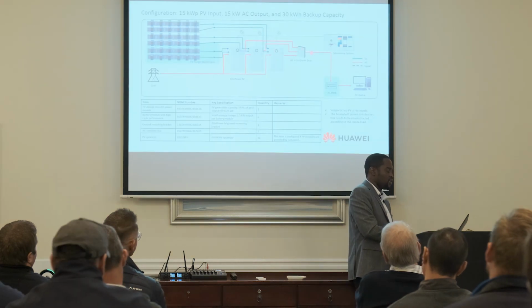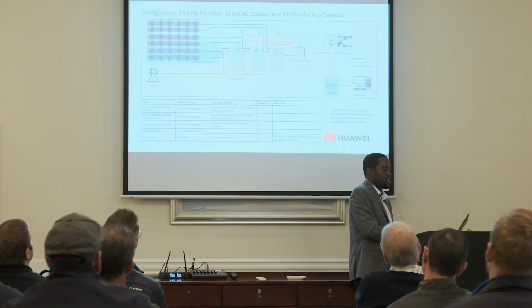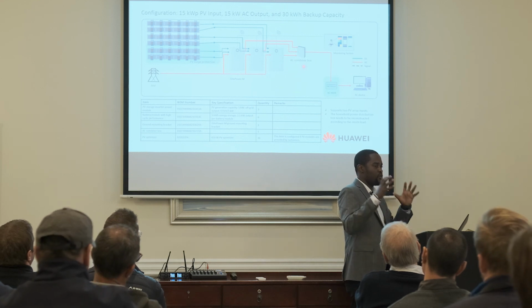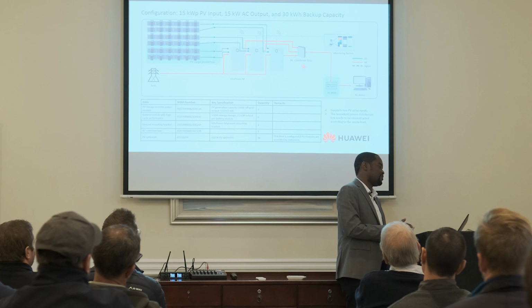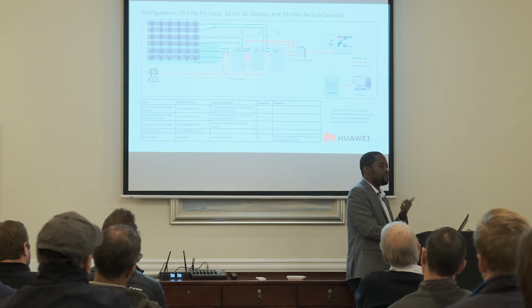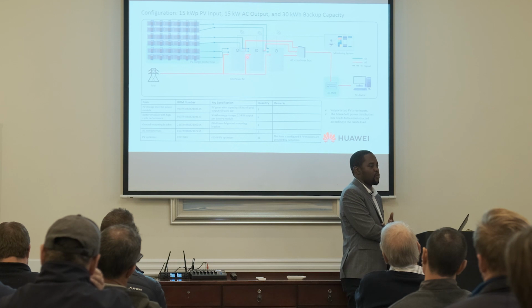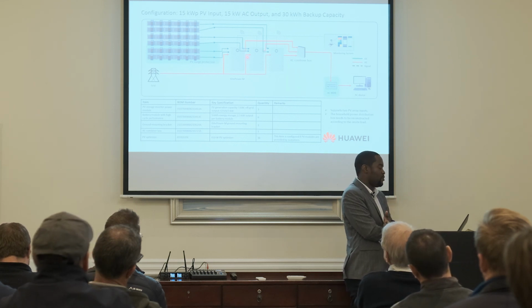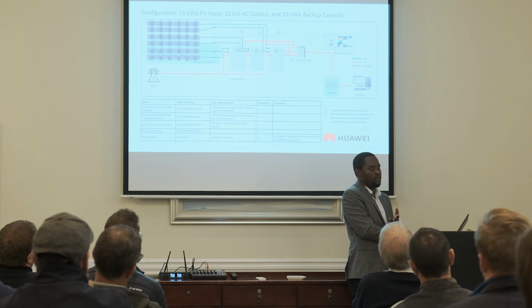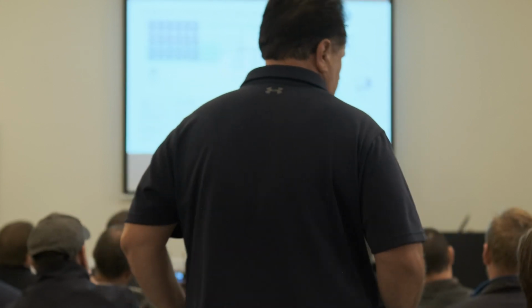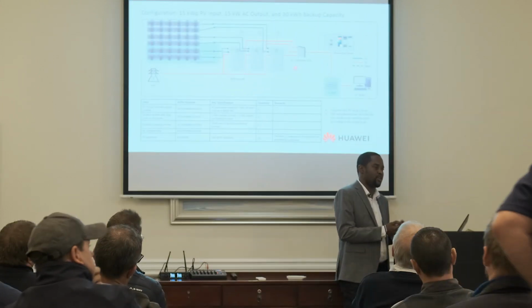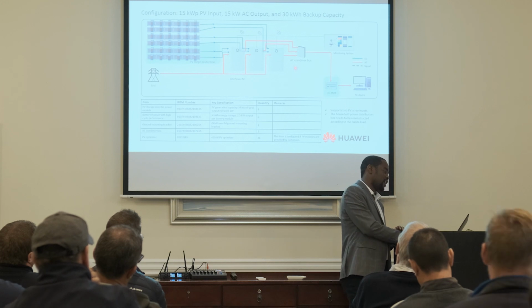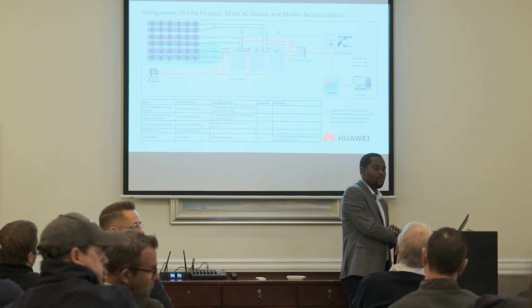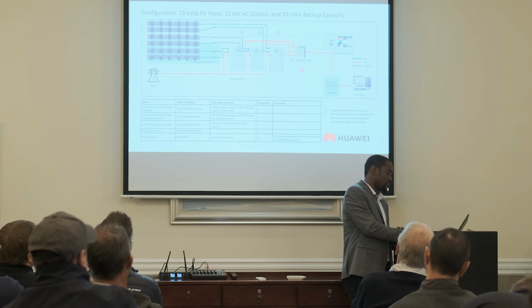Then on the output, we also recommend that you put a changeover switch. Remember the inverter AC output is where you put your backup loads. If you don't have a changeover switch and something bad happens to the inverter, then those backup loads are taking power through the inverter, so you won't have power to your backed up loads, your essential loads. So with the changeover switch, if a client calls you during the night, you can tell them, okay, please put the changeover switch on grid, then I'll arrange the team and we will come and attend to you in the morning. But if you don't have that changeover switch, then you may be forced to attend to such queries urgently.